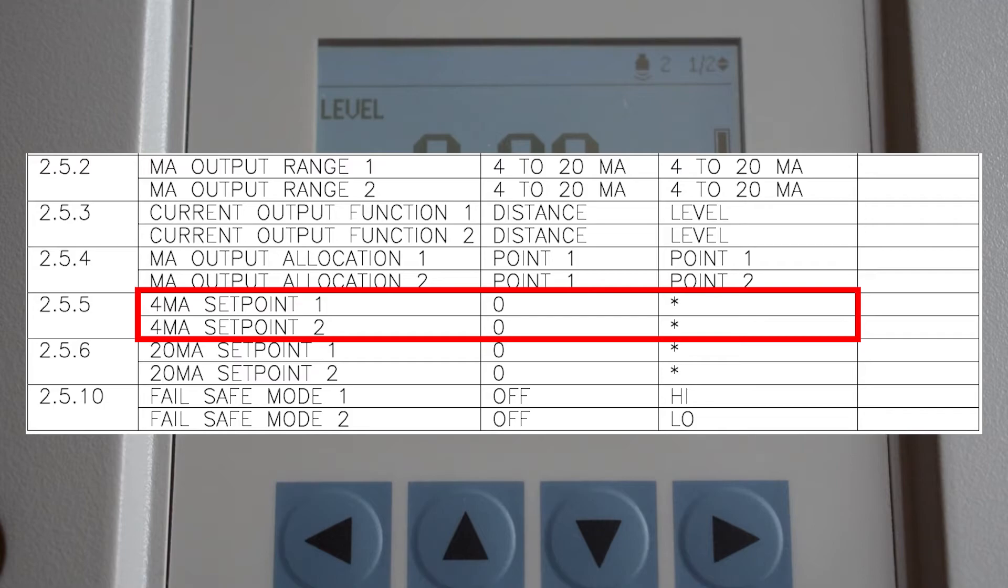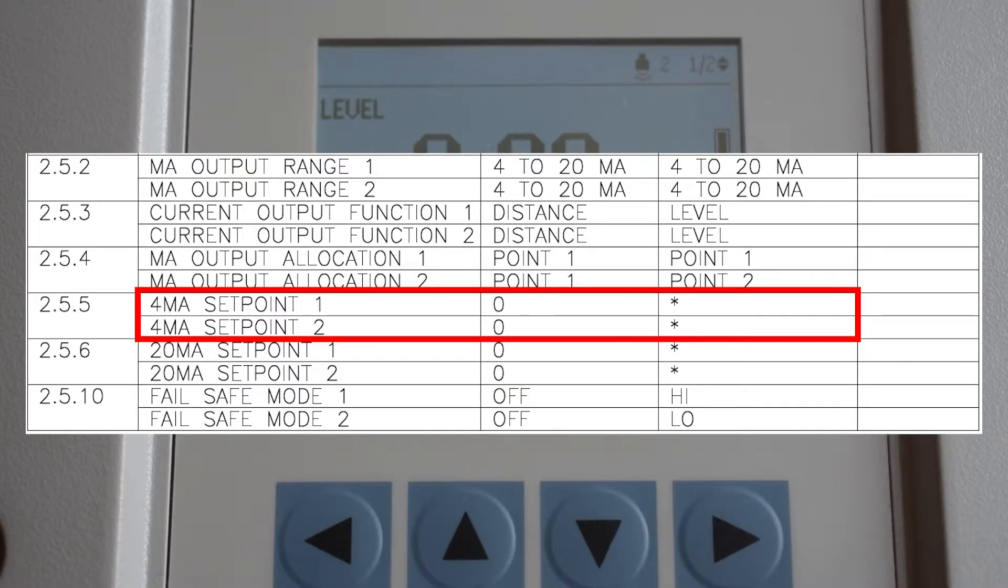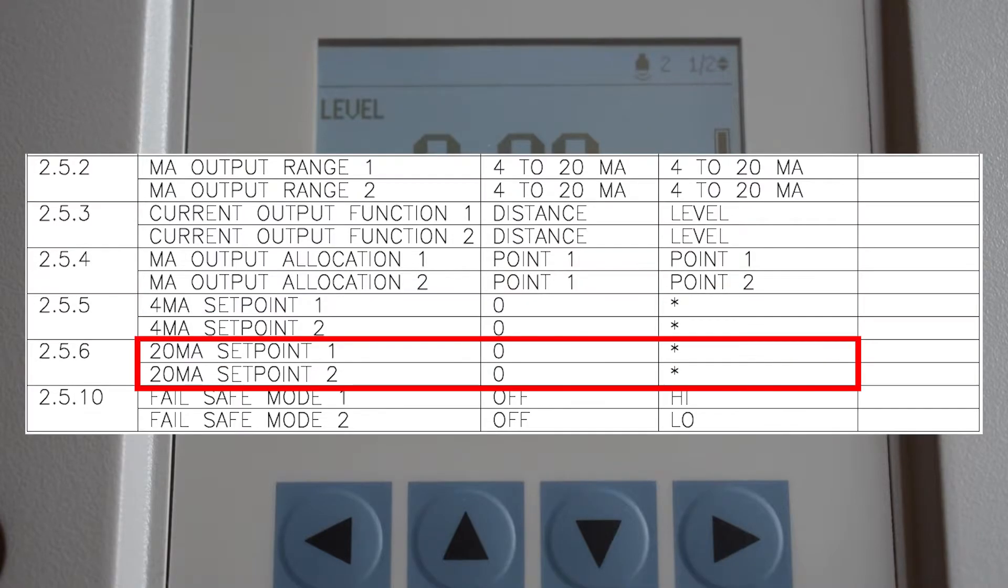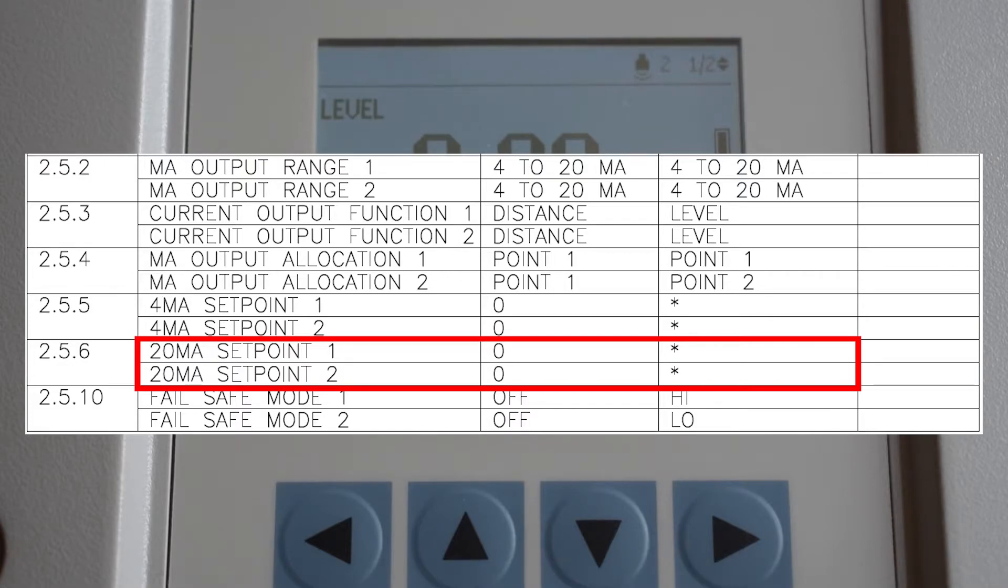The 4 milliamp and 20 milliamp set points marked with an asterisk will need to be set up by the startup technician. 4 milliamp is typically set at zero or the bottom of your measurement range. 20 milliamp is typically set to the maximum of your measurement range, which typically corresponds to what was previously set in the span parameter.